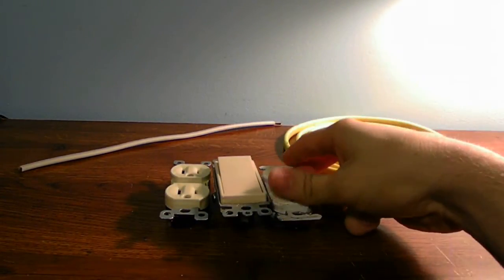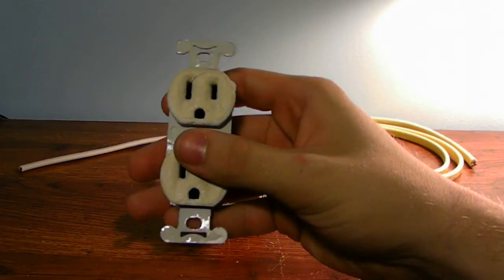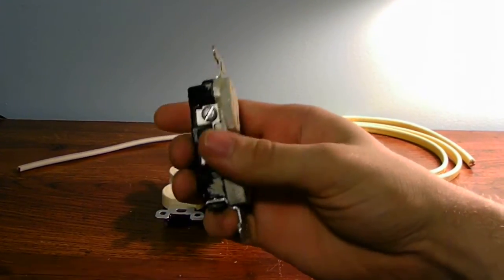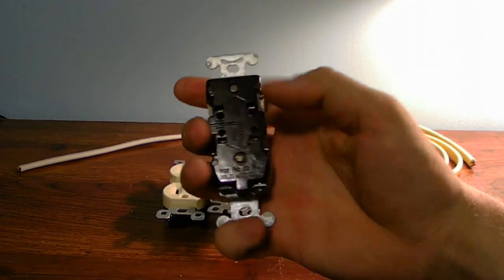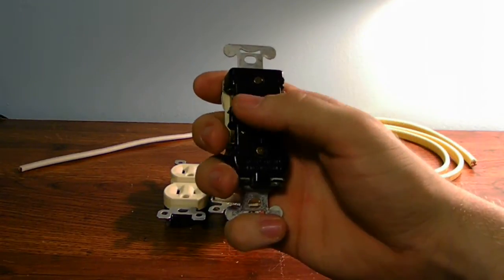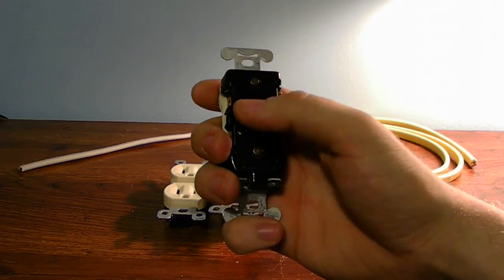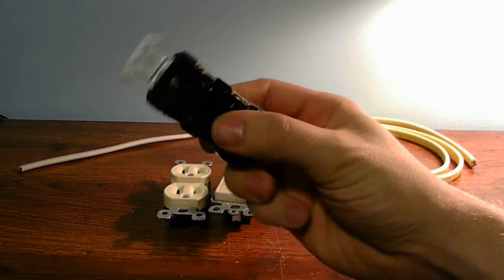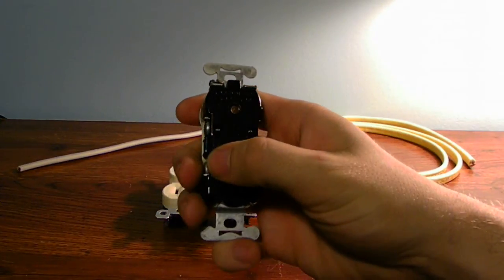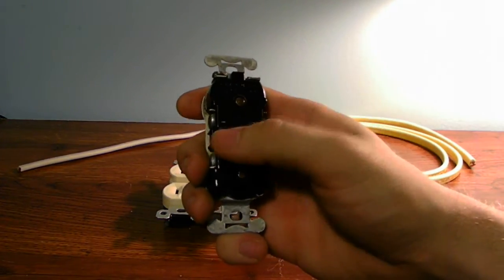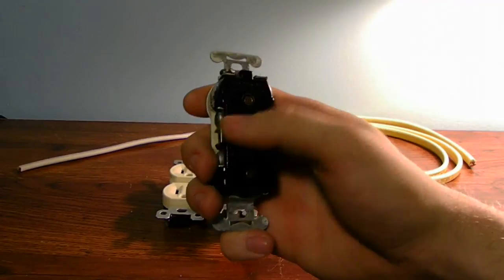And this is an older outlet, by the way. This was back-fed on these push-on terminals. These terminals do come loose over time when you have wire inside the terminal.